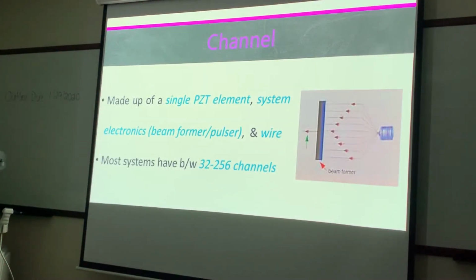And then just a recap of what a channel is. Again, guys, our original electrical signal is coming from where? The pulser. The pulser is going to send the electrical signal to the beamformer. The beamformer is going to decide how this electrical signal is going to be distributed among these active elements. So, this channel is made up of the system electronics, the beamformer, and the pulser, these wires, and the active elements within that transducer.